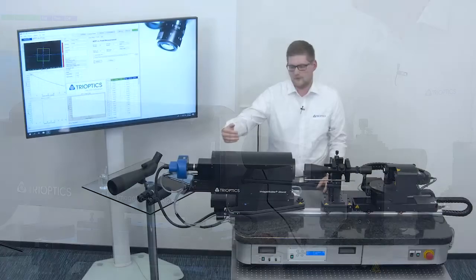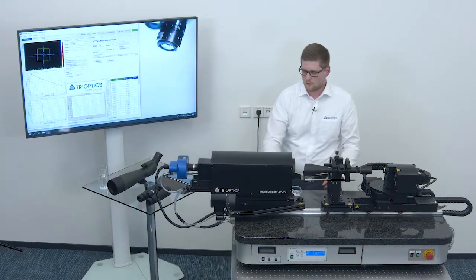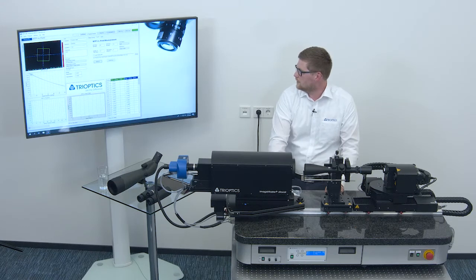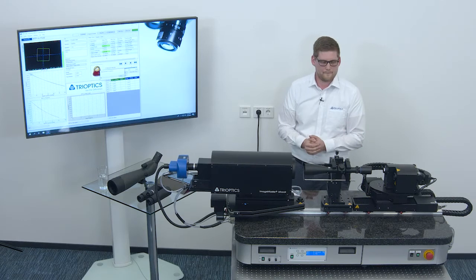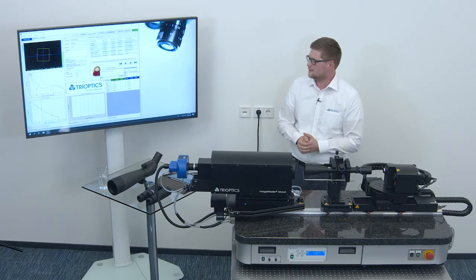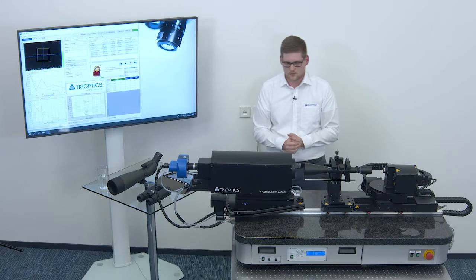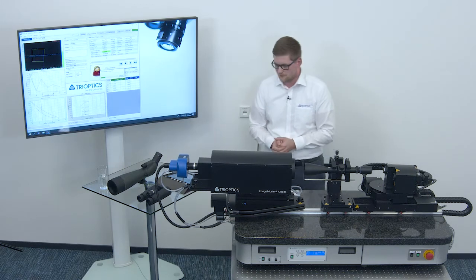We will now measure the MTF and the collimator will move from one side to the other of the field of view and the detector will follow. We will get different results for the image quality over the complete field of view.